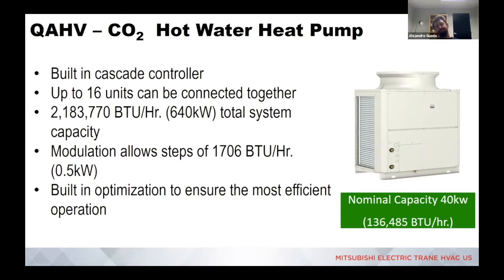Thank you. Thanks. Scott Kennedy, you had a couple questions. I'm just wondering, for the outdoor water unit for the hot water system, is it a split system with a heat exchanger, or are we actually running water right into that unit? Because we've certainly had some issues with using CO2 outdoor heat pumps and freezing up and some issues there. So I was just curious whether that's been addressed.